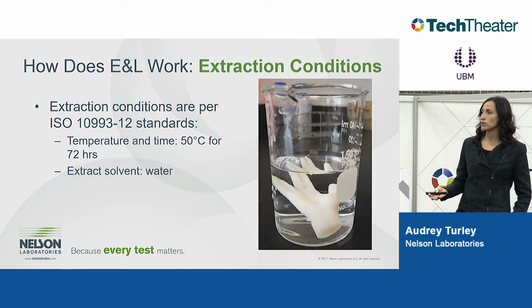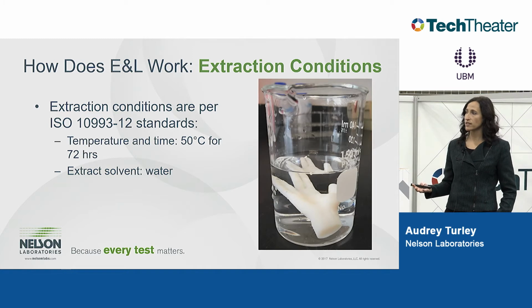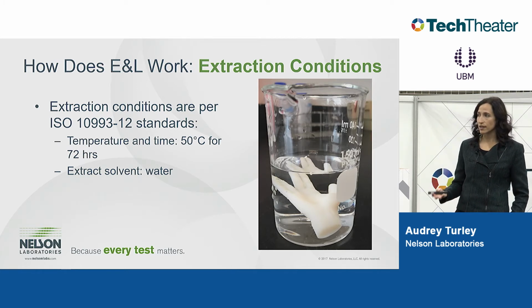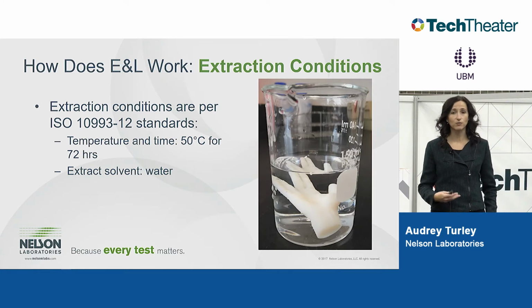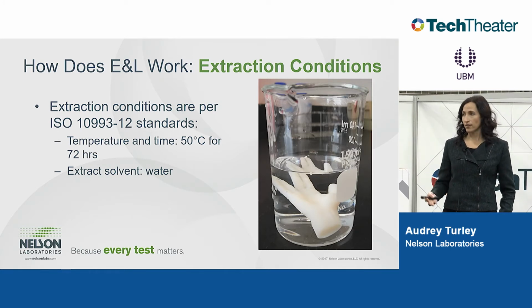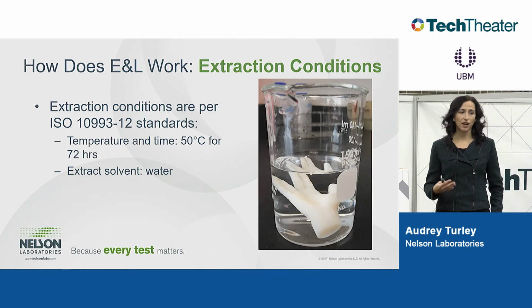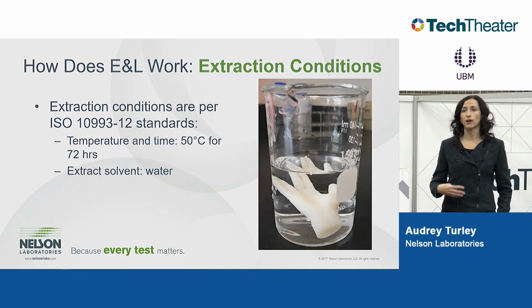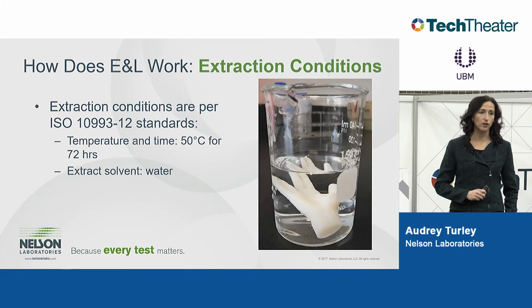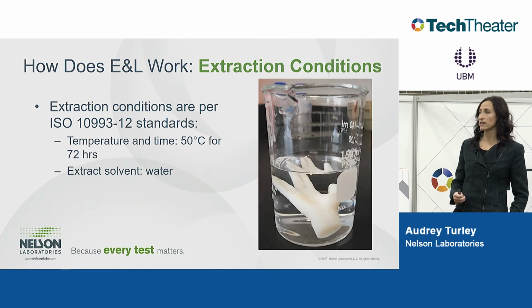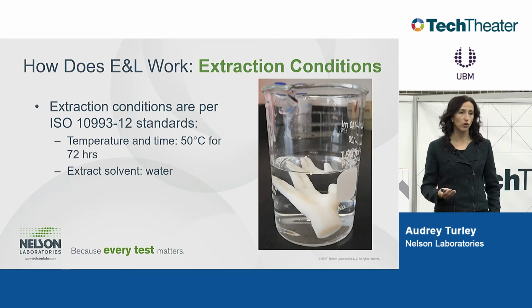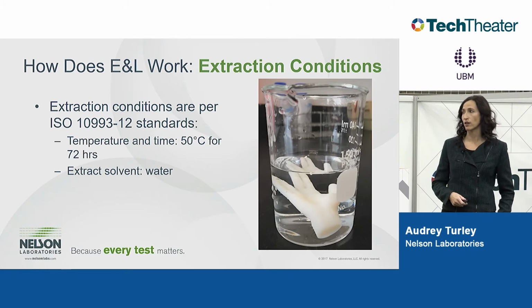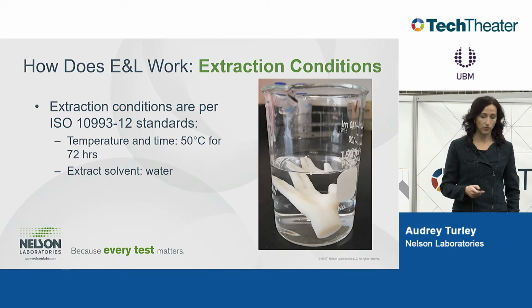Typically what we do is we run the extraction; we'll immerse the device in water at 50 degrees for 72 hours. We do just recommend using water because that is what's clinically relevant at this point. We have had success in promoting that to the FDA. I'm going to say this over and over again, that it always depends on your reviewer in the FDA. That's why a pre-sub meeting is great. Submit your biological evaluation plan. Point these things out, because with other extractable and leachable testing in the past, the FDA will want you to use a polar, a non-polar, and sometimes a semi-polar solvent. So it's important to have this conversation up front.